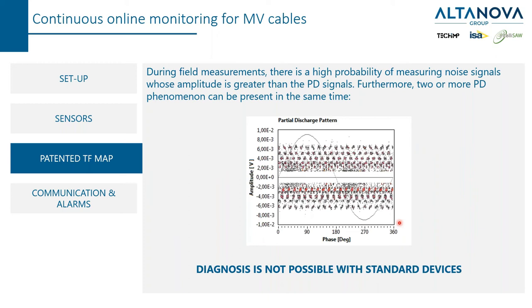When we perform a field measurement there is a high probability that we are also measuring noise, or more than one phenomenon at the same time. If we observe the measurement just from the phase-resolved partial discharge pattern, we see all the phenomena overlapped, making it almost impossible to perform an accurate analysis. We have to find a solution to solve this issue.